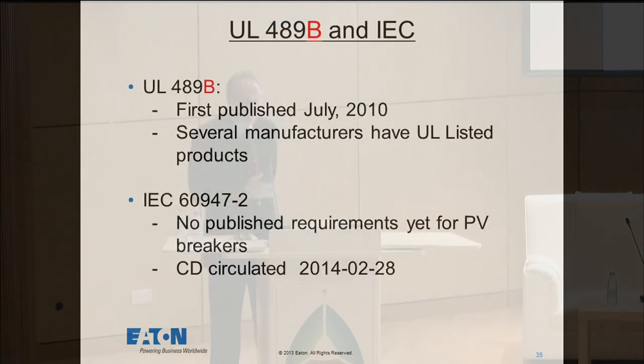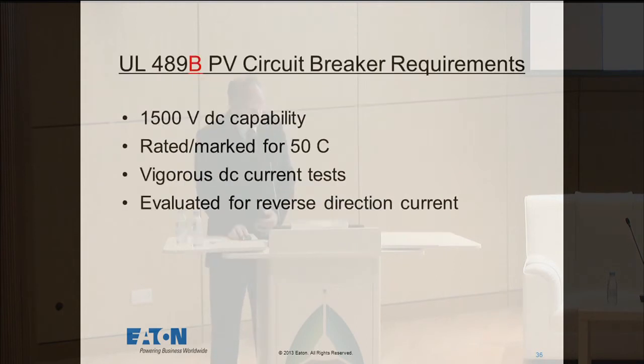This document has been published now for several years. It's been out since 2010, and there's already been revisions to it, and it's been refined. So we have this document out there. Many manufacturers offer photovoltaic circuit breakers, UL-listed photovoltaic circuit breakers. And when I go to the IEC 60947-2, today it does not have specific requirements for photovoltaic circuit breakers. They are in development. And right now it's in what's called the CD stage, the committee draft stage. So it's still going to be a while before that becomes a published standard in the IEC. And they're still working on what those requirements are. So today you can buy UL. We still have to wait for the IEC standard. And then some of the things that are unique for the photovoltaic system, which are very important, these are rated up to 1500 volts DC. The voltages on the photovoltaic systems keep being raised, and this document covers requirements up to 1500 volts DC.